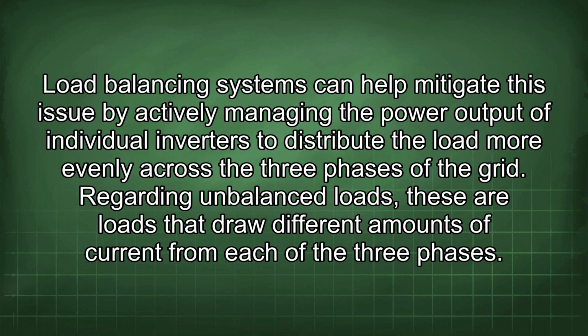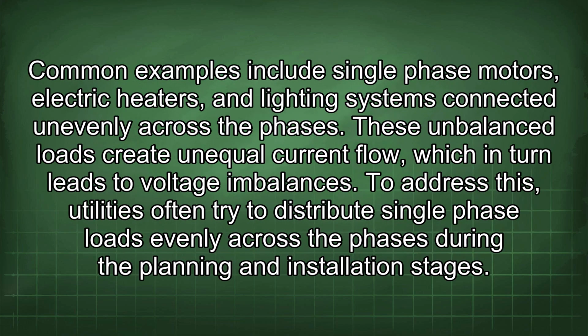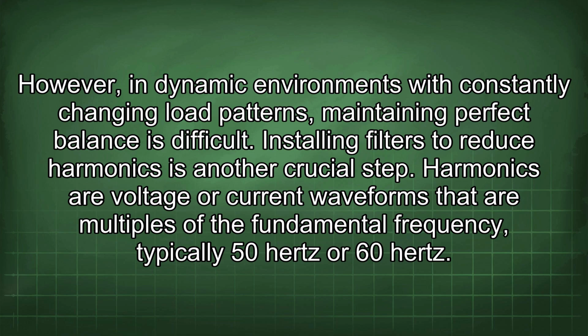Regarding unbalanced loads, these are loads that draw different amounts of current from each of the three phases. Common examples include single-phase motors, electric heaters, and lighting systems connected unevenly across the phases. These unbalanced loads create unequal current flow, which in turn leads to voltage imbalances. To address this, utilities often try to distribute single-phase loads evenly across the phases during the planning and installation stages. However, in dynamic environments with constantly changing load patterns, maintaining perfect balance is difficult. Installing filters to reduce harmonics is another crucial step.